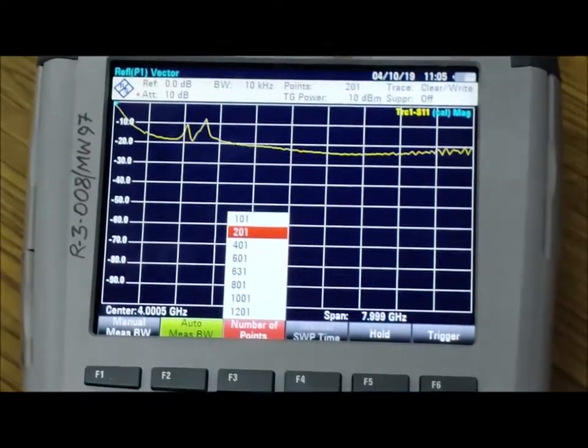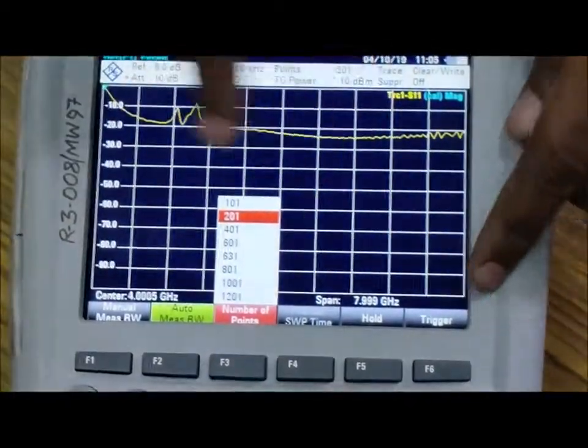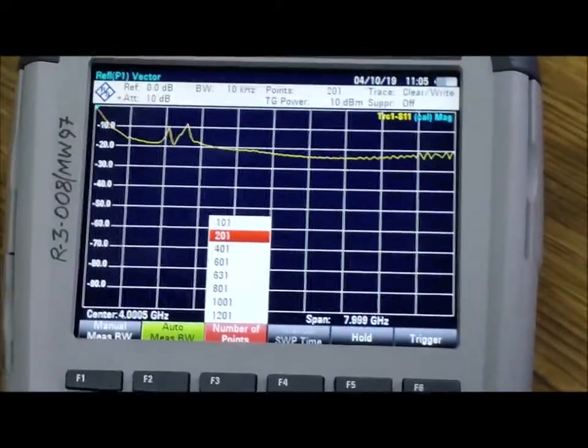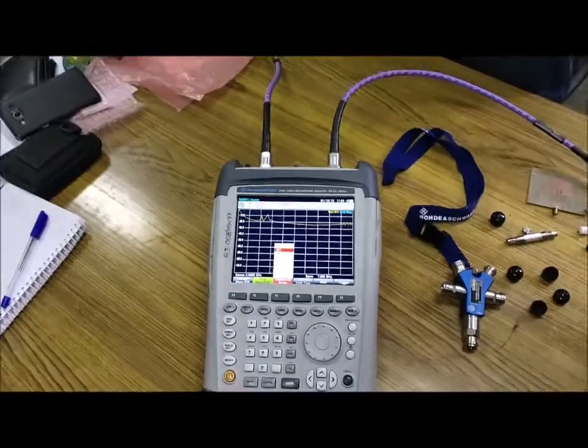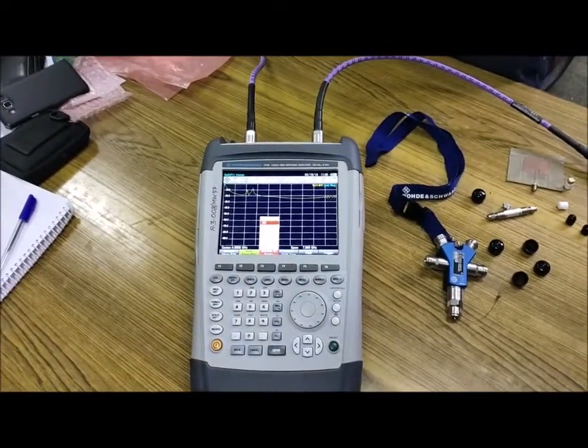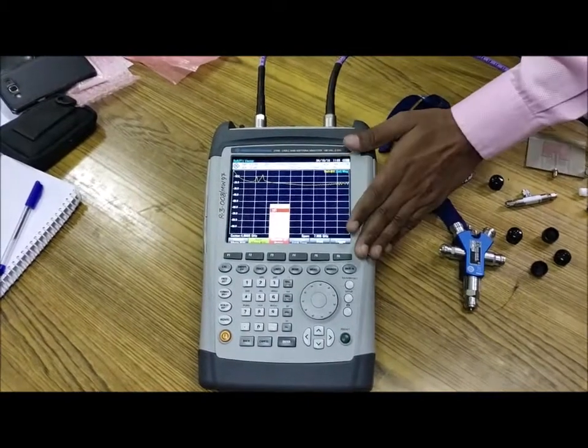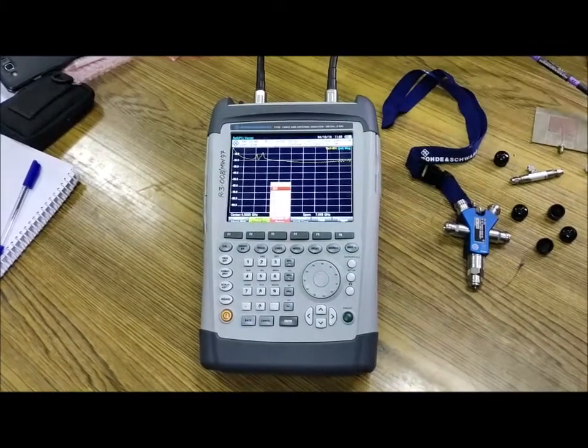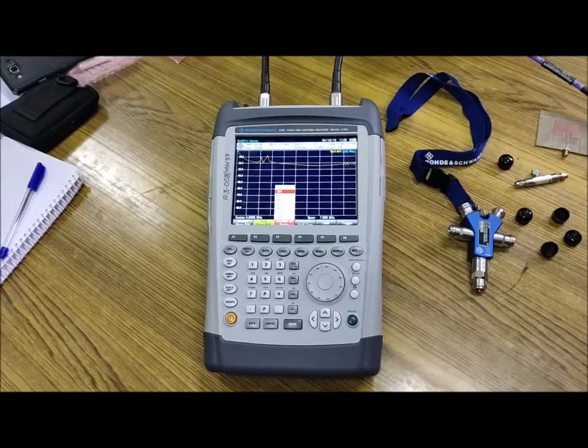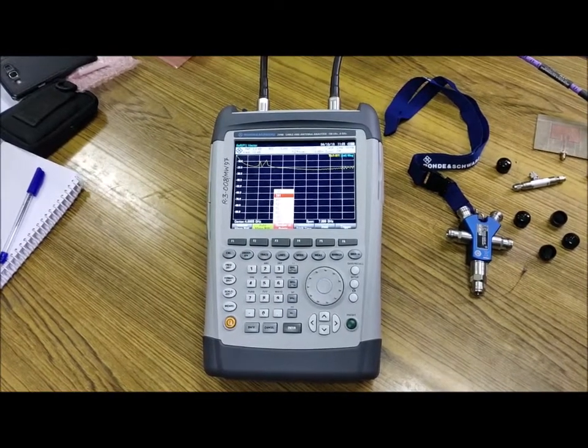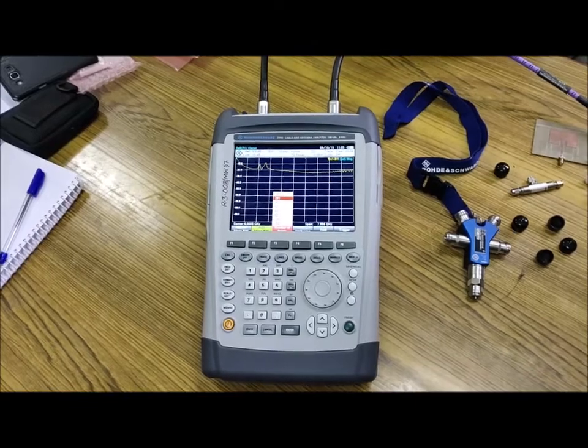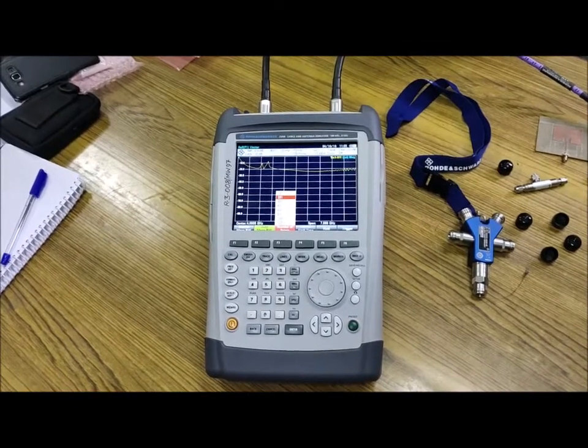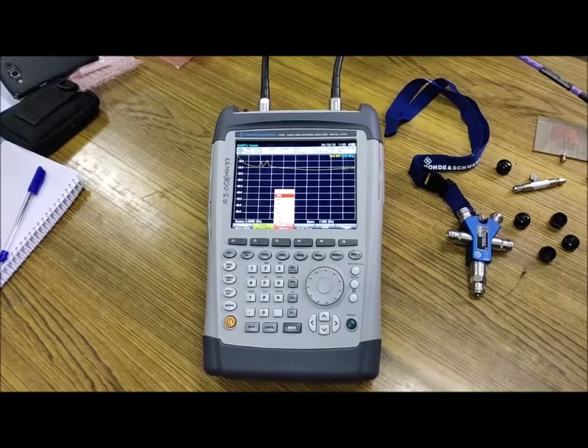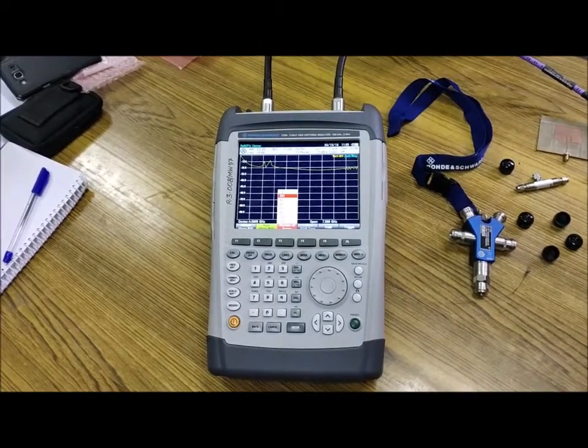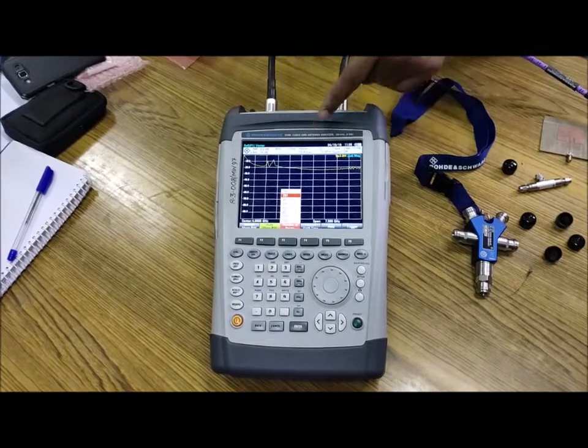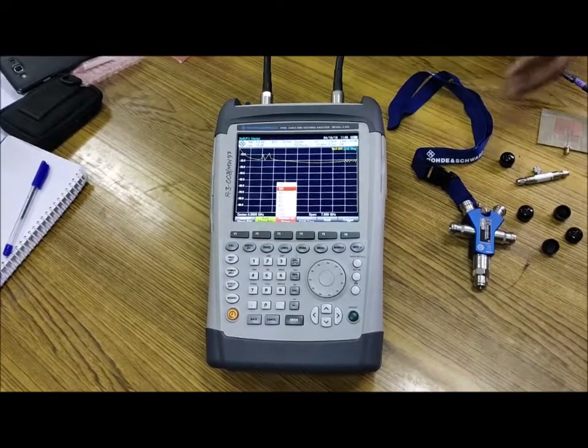I can change the number of points. In the entire frequency range, I can select that the total frequency range be divided into 101 points, 201 points, or 401 points, and so on. The maximum which this particular VNA has is 1201 points. So let's suppose from 10 megahertz to 8 gigahertz, this frequency range can be divided into 1201 points. Right now, by default, it is selecting 201 points.